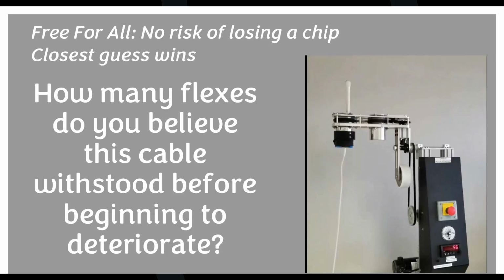So how many flexes do you believe that cable withstood before it started to deteriorate? And if you want to see an example of this, stop by the Innovatus booth. We have one of these devices. We call it a tick-tock. What it does is it oscillates the probe back and forth 180 degrees, and while it's doing it, it's twisting the scan head 180 degrees each way. So we're torturing the living heck out of that probe.